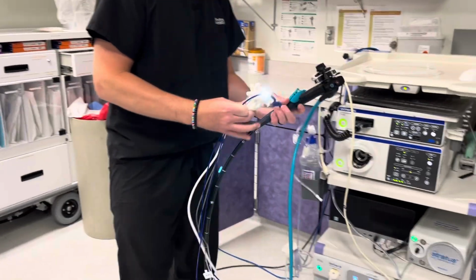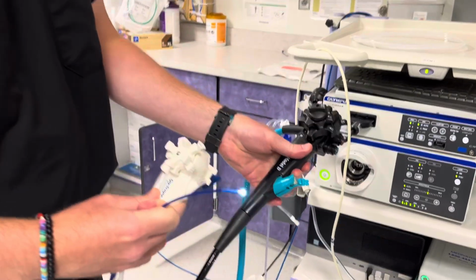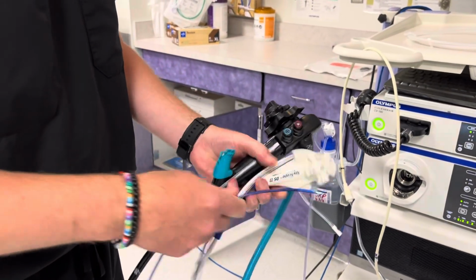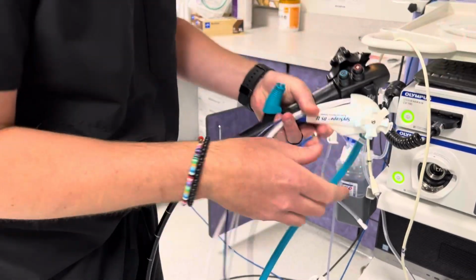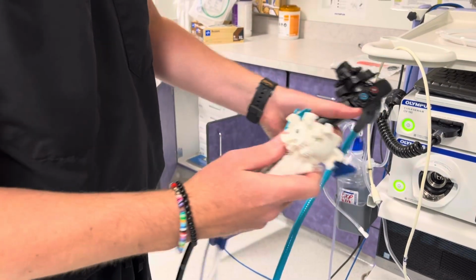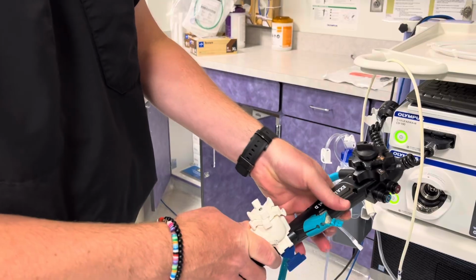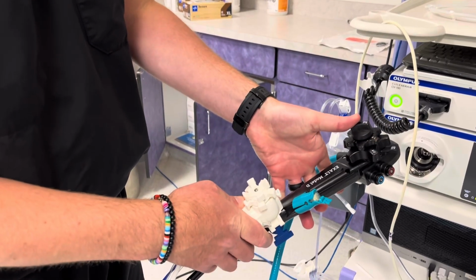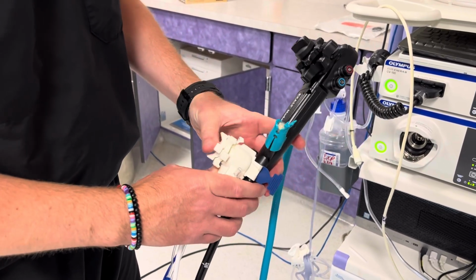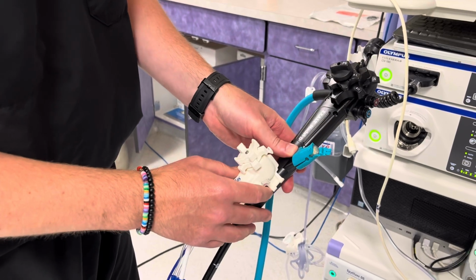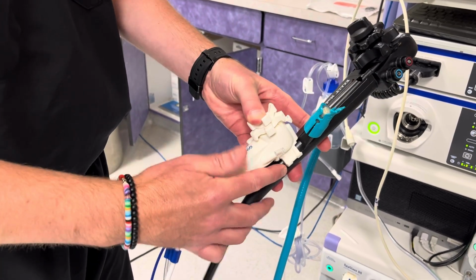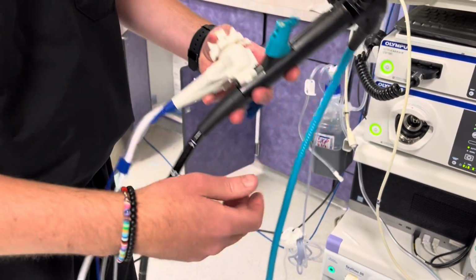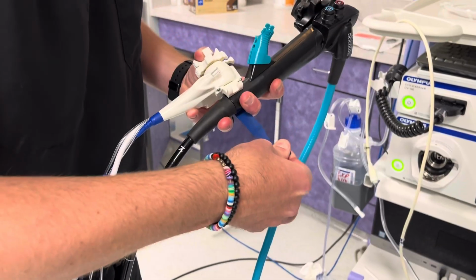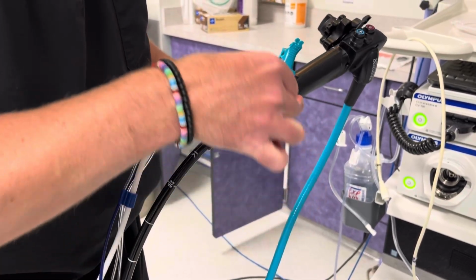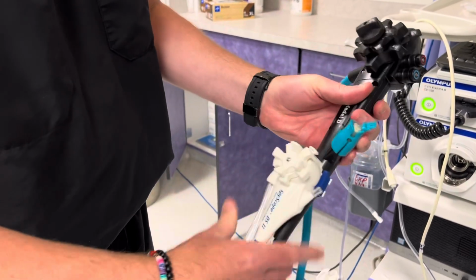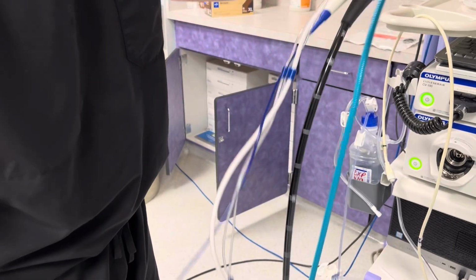Finally, your Spyglass catheter is going to be attached to the duodenoscope. Ideally what you want is you want the dials of Spyglass to be in line with the dials of the duodenoscope. And what we're going to do is go directly below the biopsy port as far as height location on the scope. We're going to pull this blue tab out and away from the handle and then wrap it around, lock it on the scope.